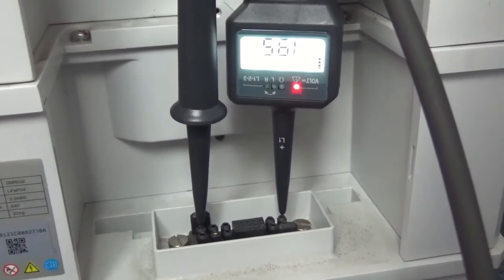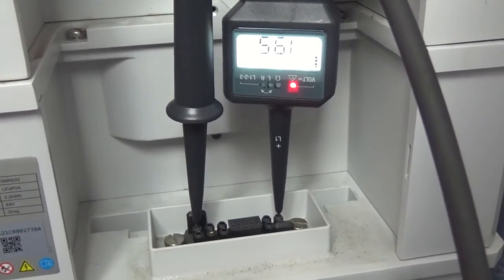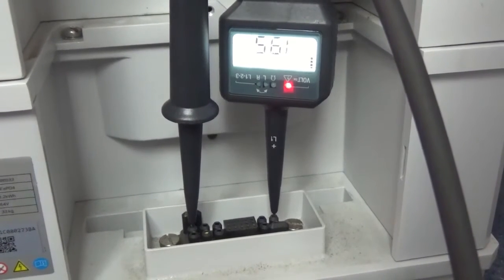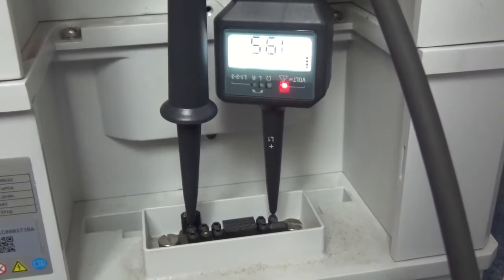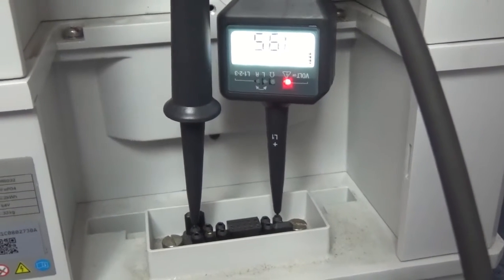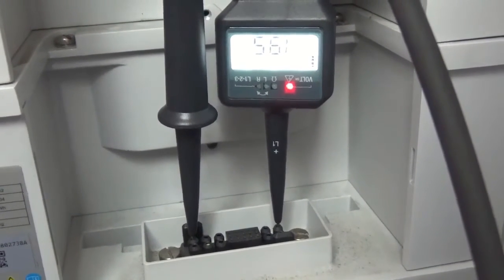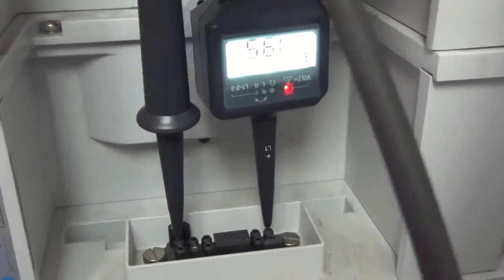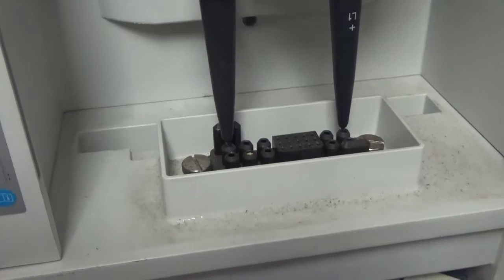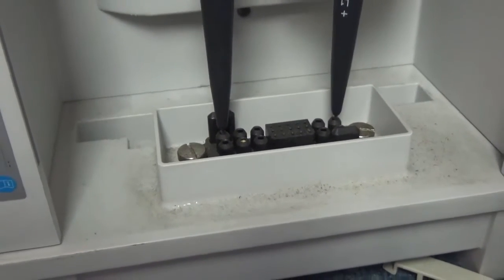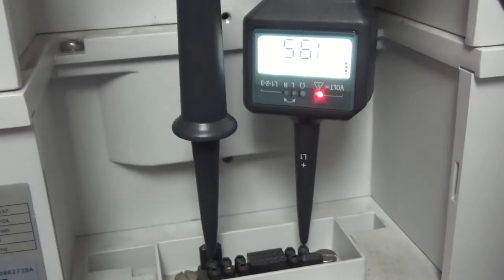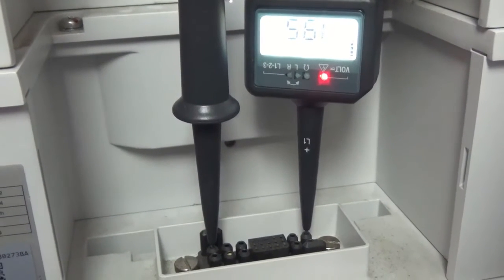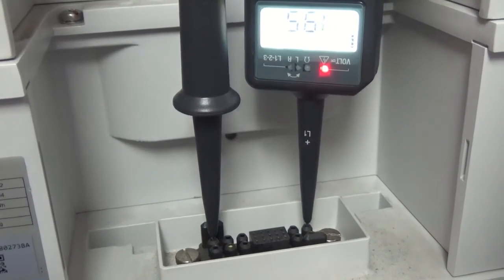Now I've removed the CMU, which is the circuit breaker box, and I've replaced the lid back on. We now need to check down at this bottom terminal. Because there's a camera pointing at it I've had to do this in advance. You see the back right hand terminal here, this is the positive terminal, and the back left hand one is the negative terminal. As you can see here I have 195 volts DC correct polarity, so we're good so far. I just need to continue working backward.